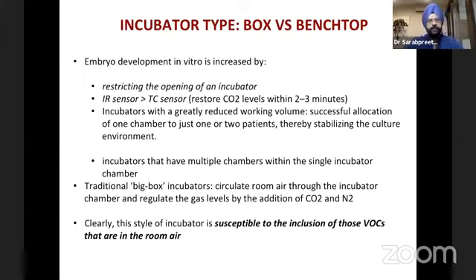The last topic, I think, for the day is the incubator type, box versus benchtop, because this is a very important part of culture conditions. Embryo development in vitro is increased by restricting the opening of an incubator using an IR sensor, and by incubators with a greatly reduced working volume, successful allocation of one chamber to just 1 or 2 patients, using incubators with multiple chambers. Traditionally, big box incubators circulate room air through the incubator chamber and regulate the gas levels by the addition of CO2 and nitrogen.